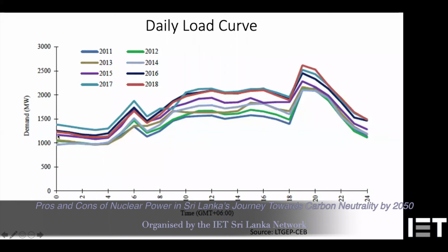As per stability simulations and studies, the largest unit in the Sri Lankan system cannot be more than 25% of the demand at that time. The demand is lowest during the early hours of the day. For example, taking the 2018 line, demand may be 1,250, and 25% of that is just about 300 megawatts, so we can run our Norochcholai 300 megawatt unit without derating it.